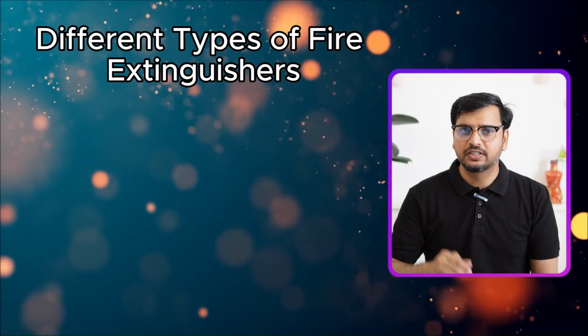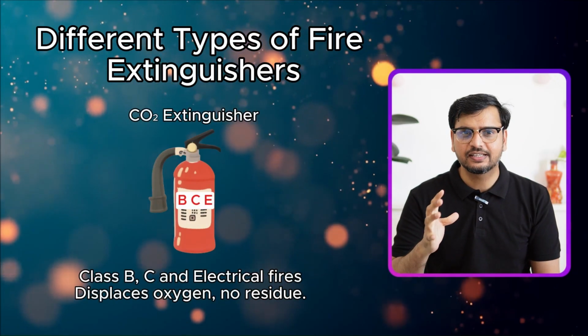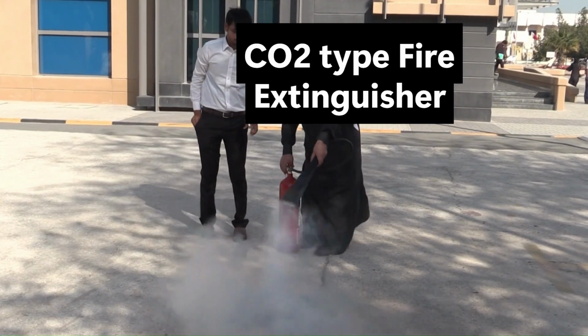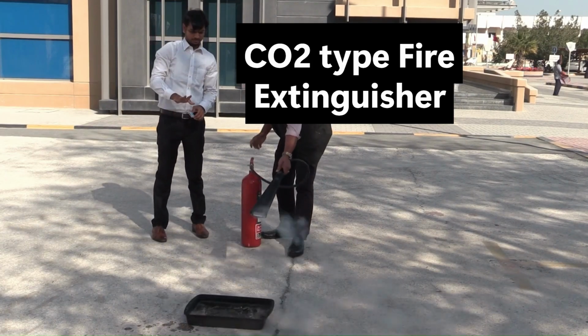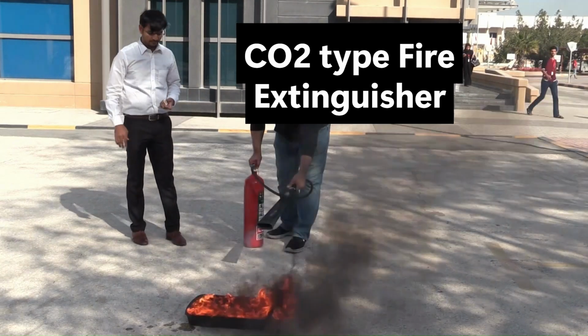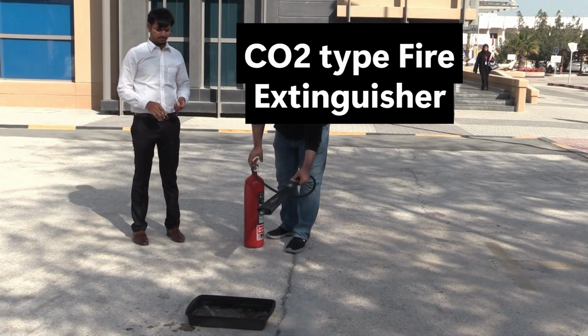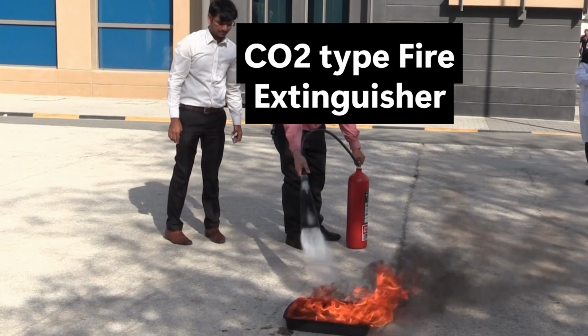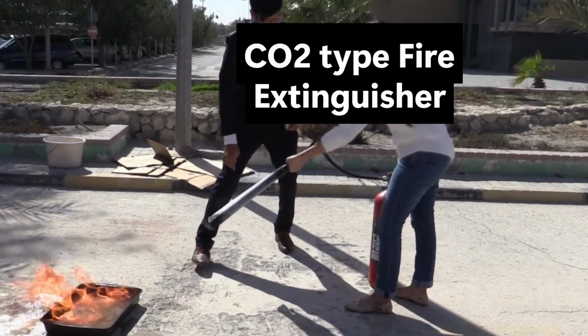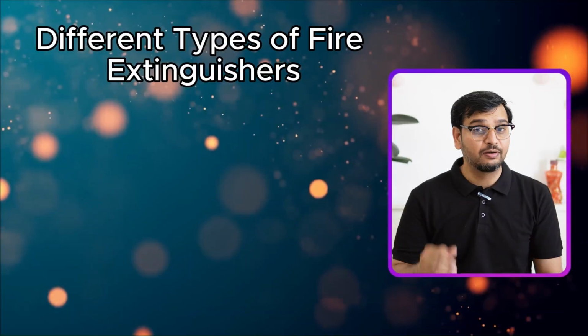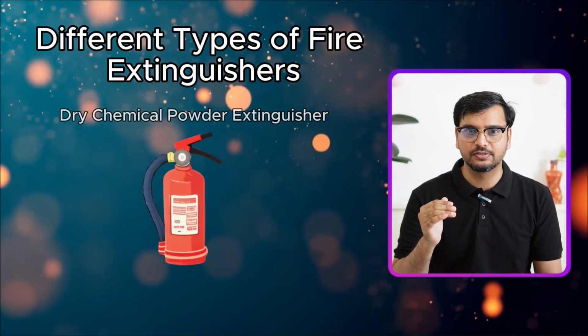So the next extinguisher is carbon dioxide extinguisher. This extinguisher is generally used on flammable liquid, which is class B fire, and electrical fire. CO2 works by displacing the oxygen that fire needs to burn, and it's safe to use on electrical fires because it doesn't leave residues.